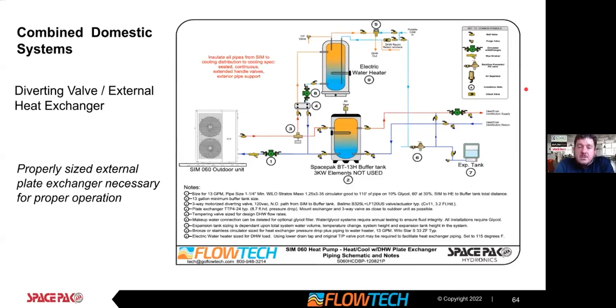So DHW is a question that we get asked a lot. As I mentioned earlier, domestic hot water, heating and cooling all from one outside unit. There's no real silver bullet with heat pump water heating for the domestic side. SpacePak does a great job of this. How it works is that the unit has, I'm looking at the SIM unit here, and I don't believe the DHW feature is available on the low ambient split unit, but if it's a monoblock SIM unit, both the 3-ton and the 5-ton, has a DHW priority call, much like a condensing boiler where you have a DHW priority. So in normal operation, whether it's heating or cooling, the unit's feeding the buffer tank.